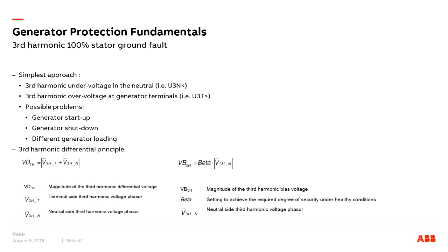Okay, so the simplest approach is third harmonic under voltage in the neutral and third harmonic over voltage at the generator terminals. The possible problem with this approach is that this protection may not be effective during generator startup and generator shutdown or different generator loading conditions, because, as I mentioned, the third harmonic will be fully available only when the generator is in its full load condition.